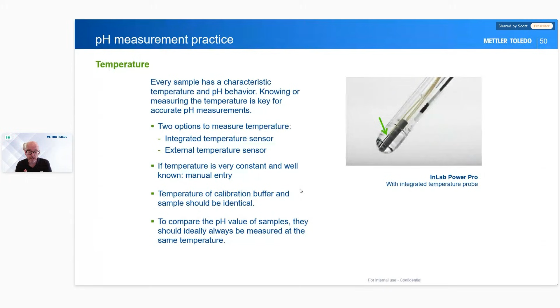If we've got very, very small samples, that's really difficult. Especially when we've got electrodes like this one, the Ultra Micro Pro, for measuring very small samples. If we do need to do that, then the best thing to do is to heat the electrode to the same temperature as you're taking your sample. At room temperature, that's not a problem.